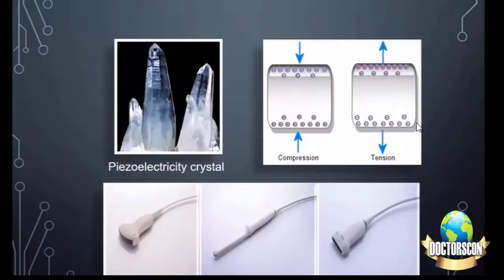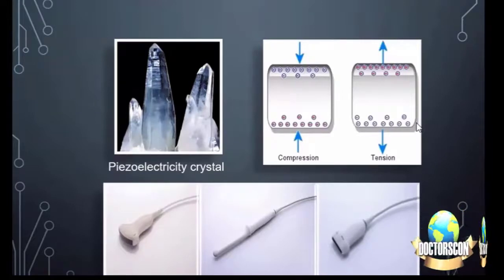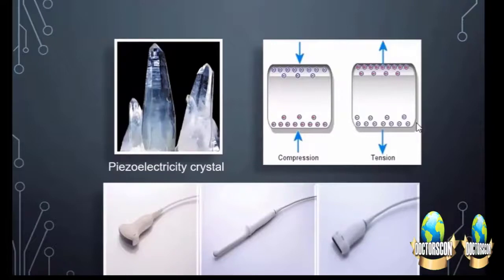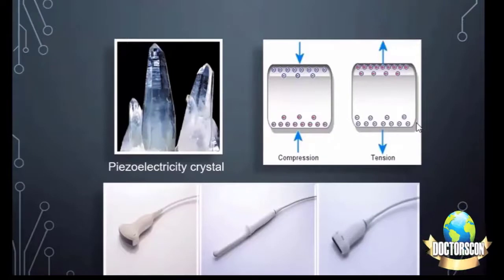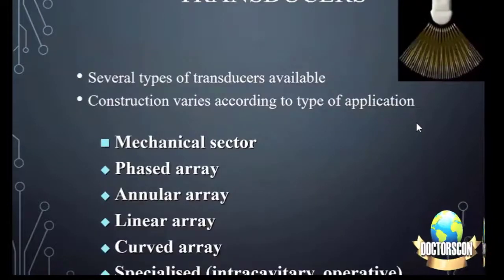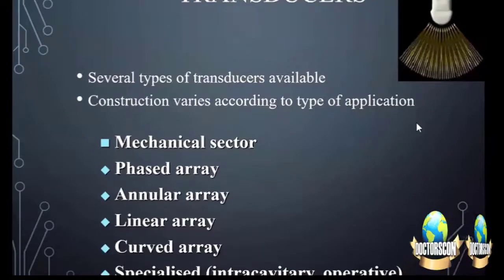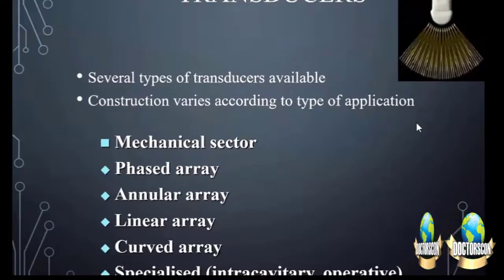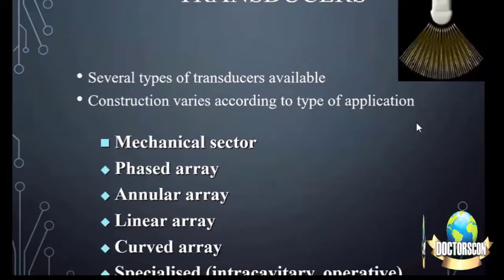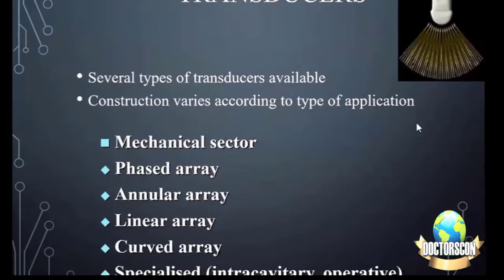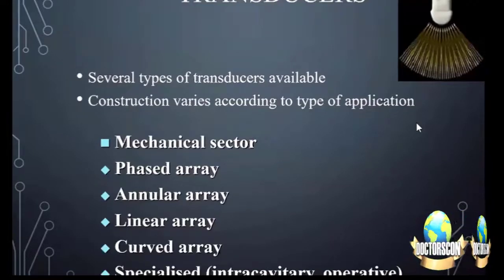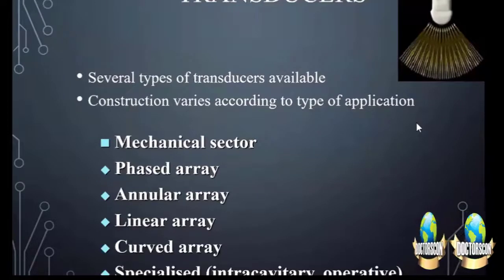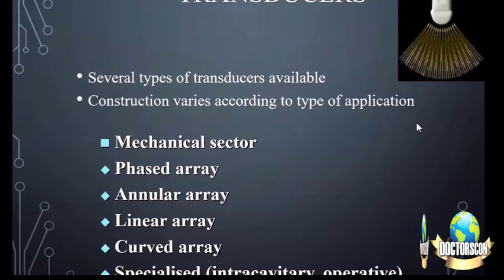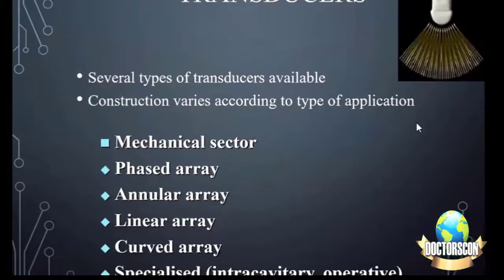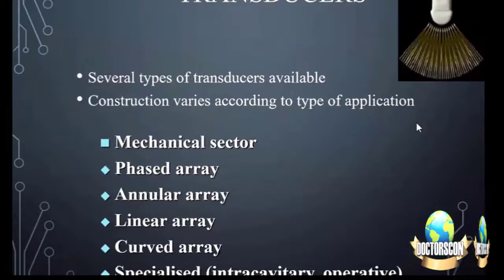There are several types of transducers available. The construction varies according to application, like mechanical sector, phased array. We can have annular, linear, curved, and specialized, the intracavitary, which are the operative ones. Piezoelectric crystals are materials which produce a voltage when deformed by an applied pressure and produce a pressure when deformed by an applied voltage. So when we give them voltage, they produce pressure, and sound waves are pressure waves.